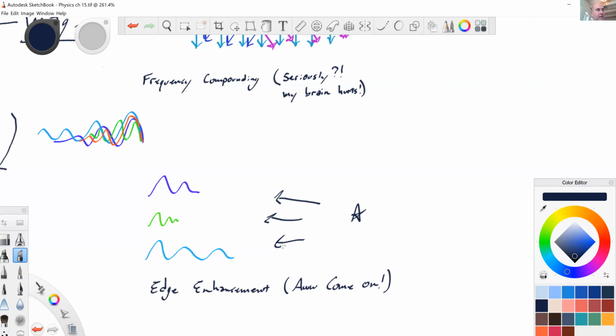So it reads in the last paragraph here, it is as if multiple images were created from transducers with different frequencies. The noise components of the reflections are different for each subband, meaning each subfrequency. And when combined, the noise level is reduced. So I'll just repeat again with the 3: the 3 separate frequencies are processed separately. It's as if you make a picture out of the purple, a picture out of the green, and a picture out of the light blue. And then you add those pictures together, and that's what you have. That's, in a nutshell, frequency compounding.